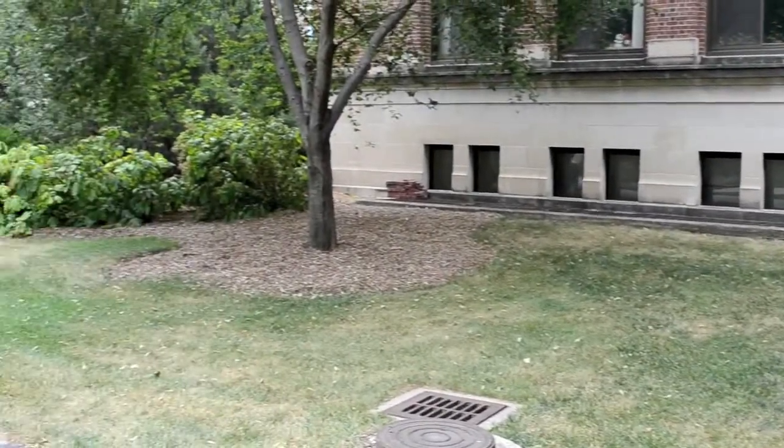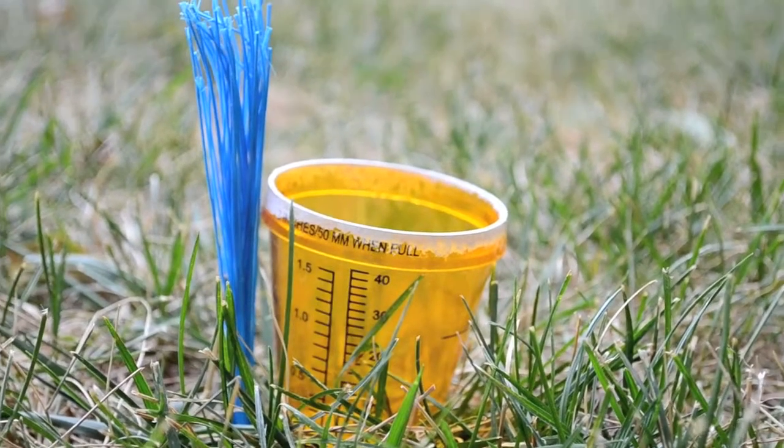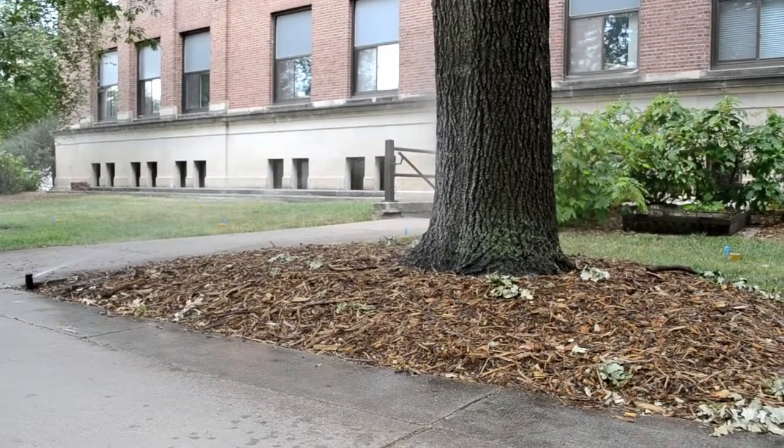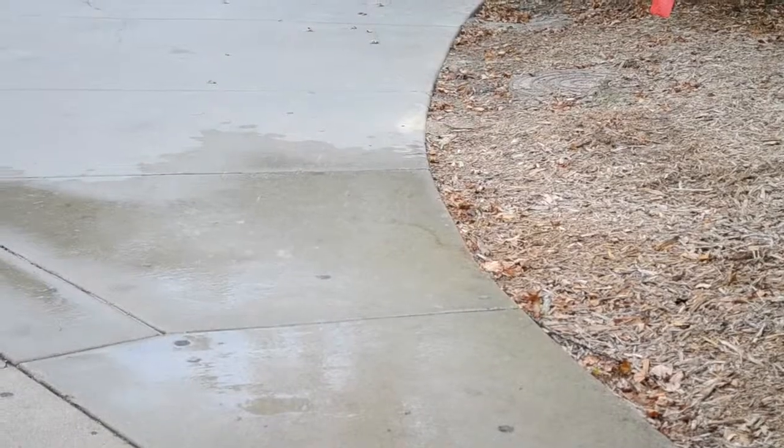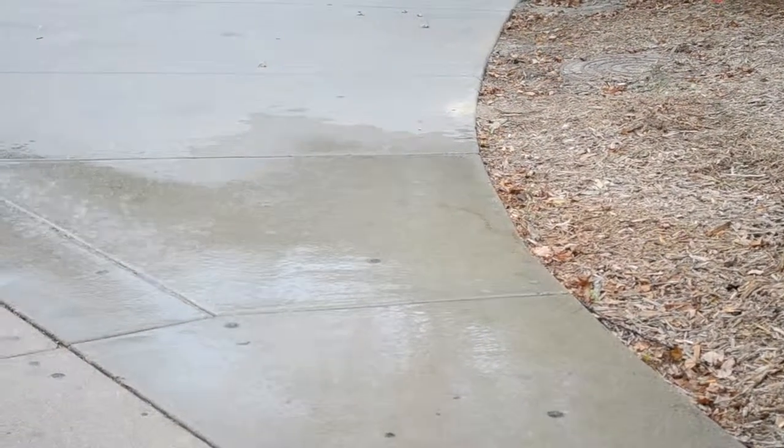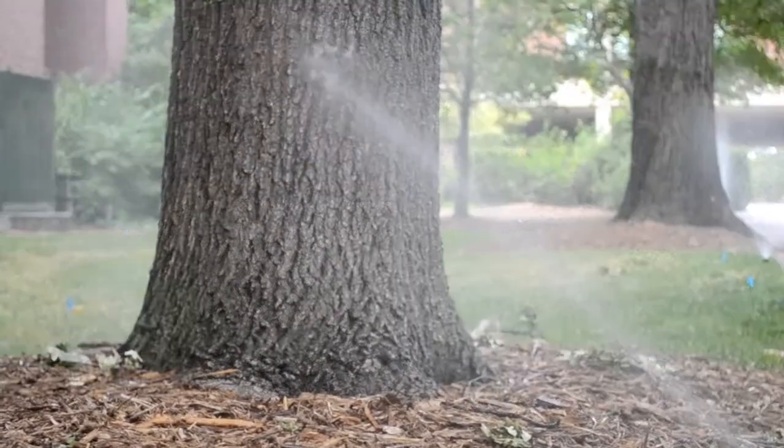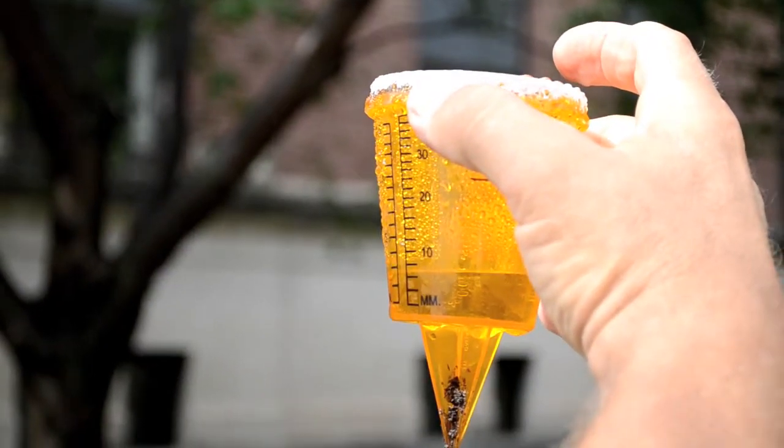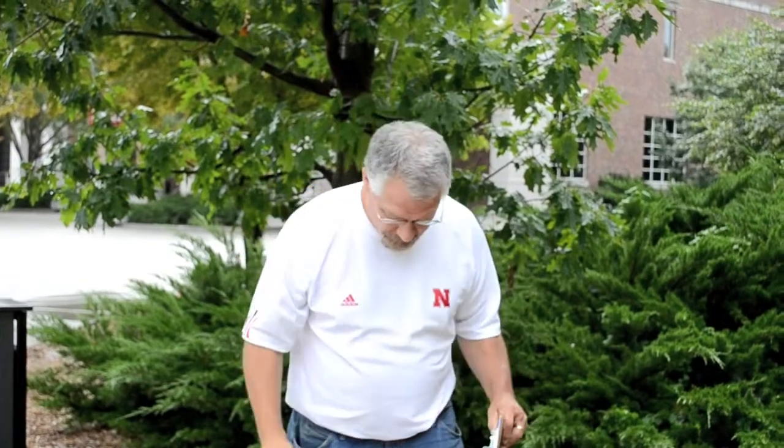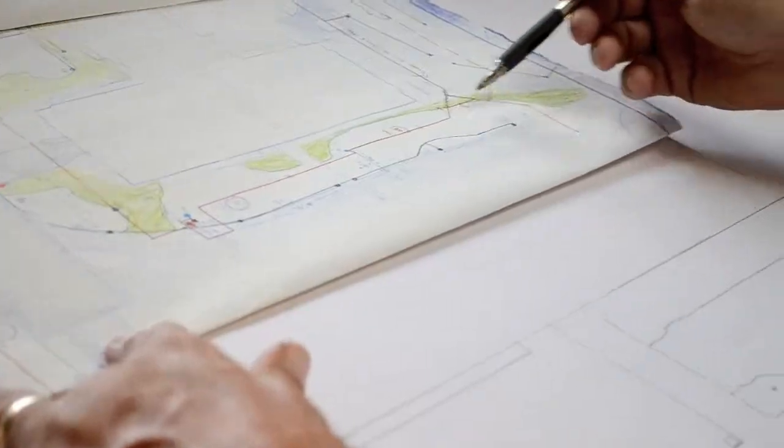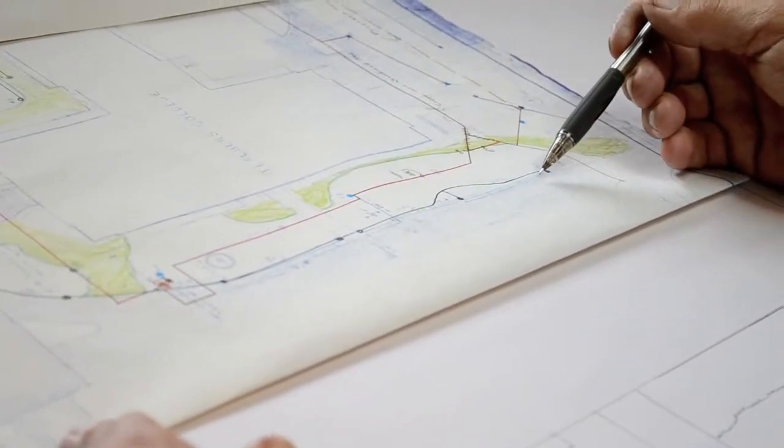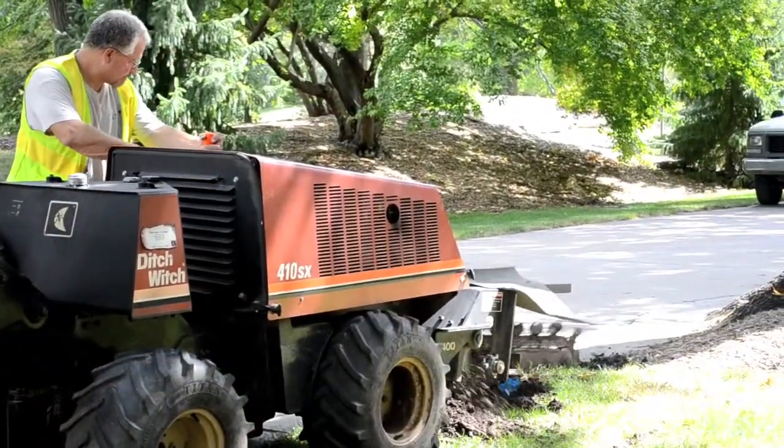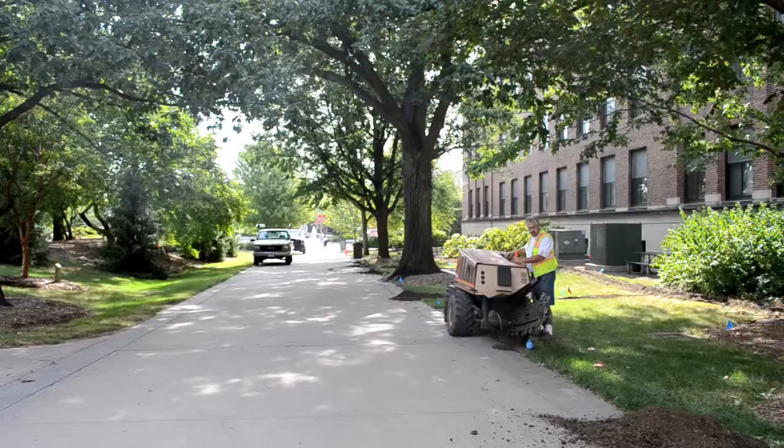Okay, here we are at the test lot. We're placing out catch cups. I'm marking them so I can return back to each spot when I do my second test. Ouch! That hurts. Look at that water. That's what we want to avoid. The water being hitting the trees, hitting the sidewalk. And if a picture is worth a thousand words, check that out. Here I'm taking measurements of my first test. And now I'll take a measurement of my second test. I want to make sure that I've got the same weather conditions and the time of day on each of my tests. We plan our work and work our plan. The fellows install efficiently. We move in on it. It's a little bit drastic, but when we saw sprinkler head hitting the tree and so forth, we wanted to make changes to improve that.